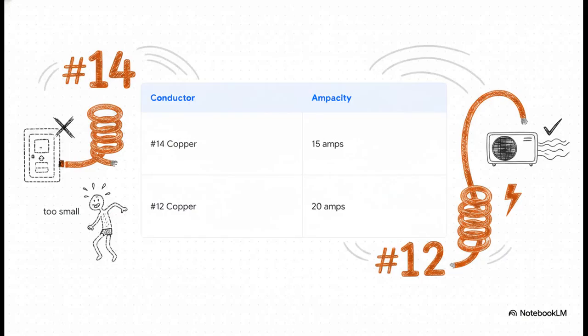Next, we take that 17.8 amp MCA and head straight over to NEC Table 310.16, specifically the 60-degree copper column. Looking there, a number 14 copper wire is rated for 15 amps. Well, since our MCA requires 17.8 amps, that 15 amp capacity of the number 14 wire just isn't going to cut it. It's too small. That pushes us up to the next standard size, which is number 12 copper wire. That gives us 20 amps, safely exceeding our 17.8 requirement.